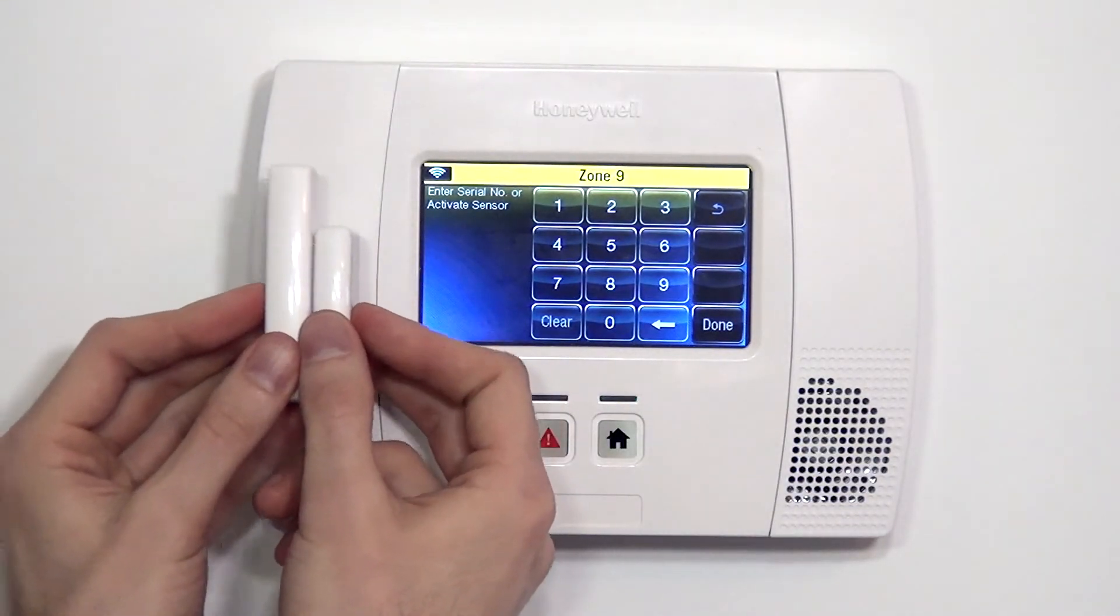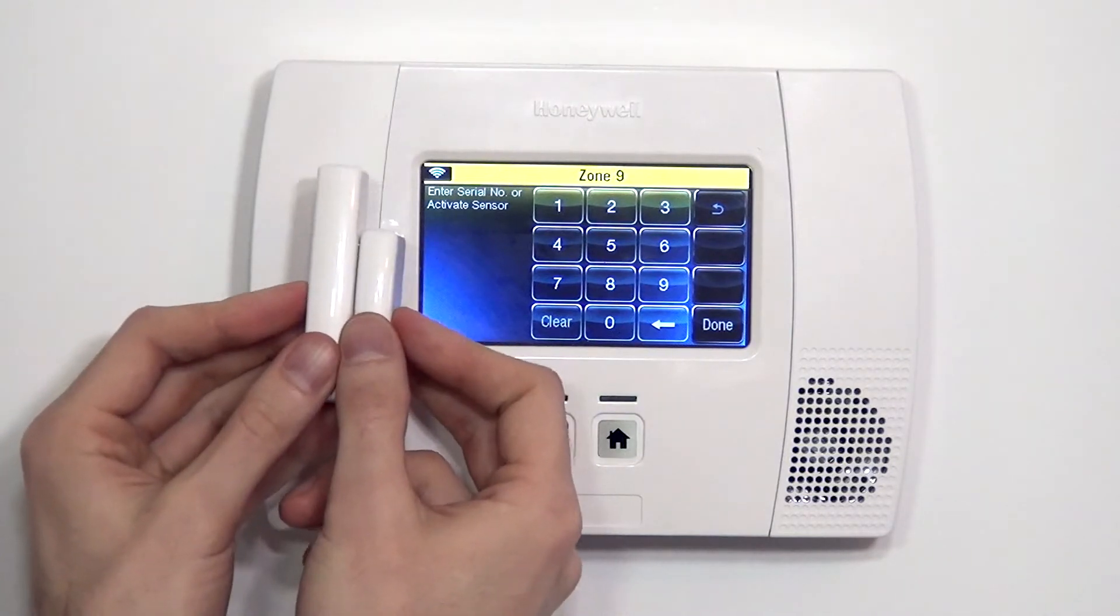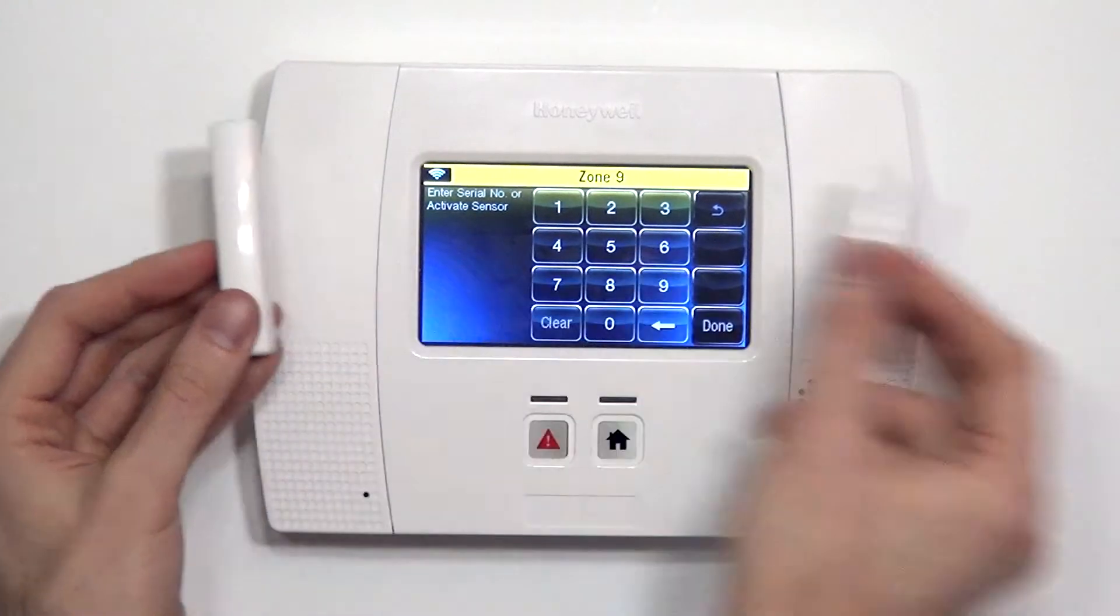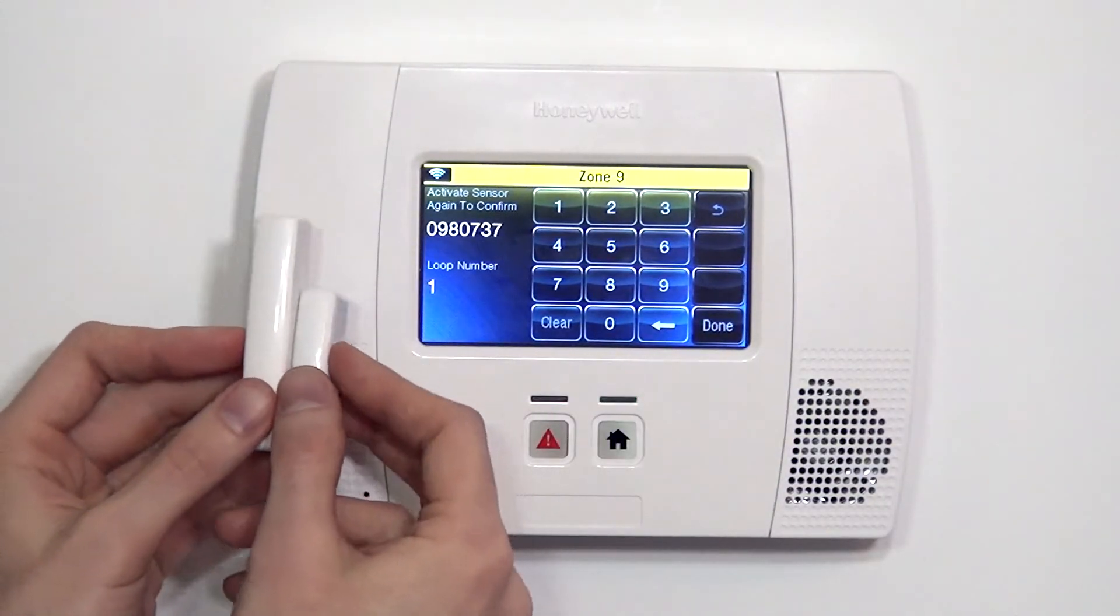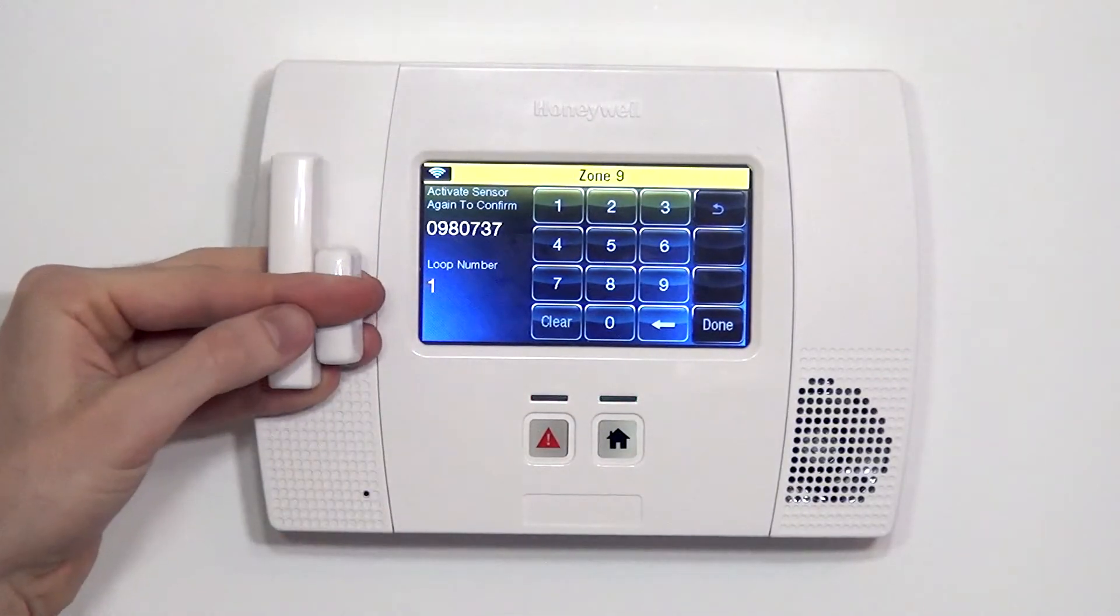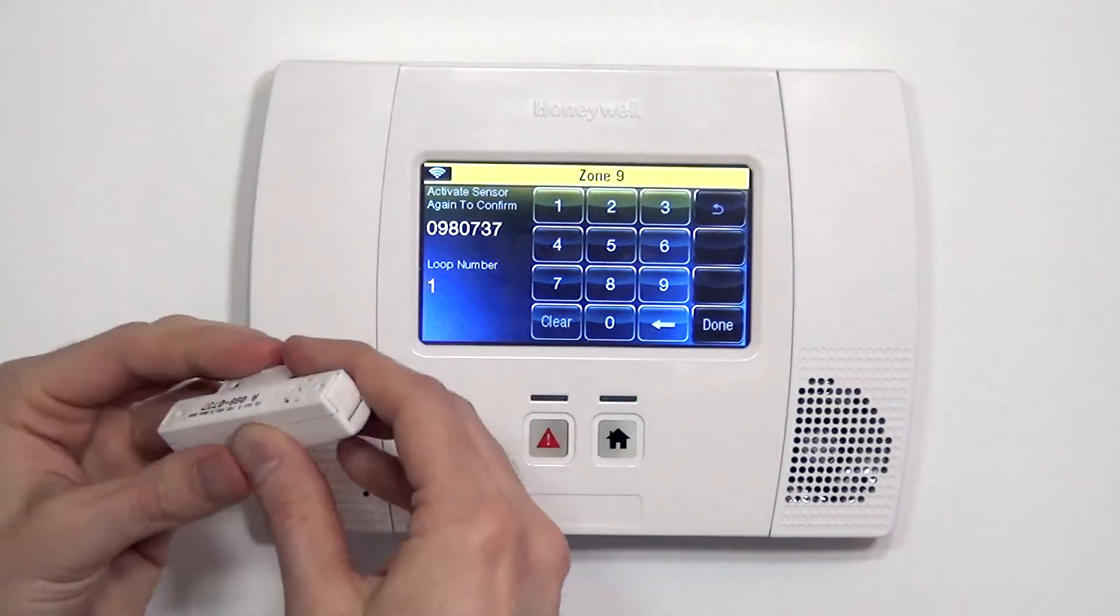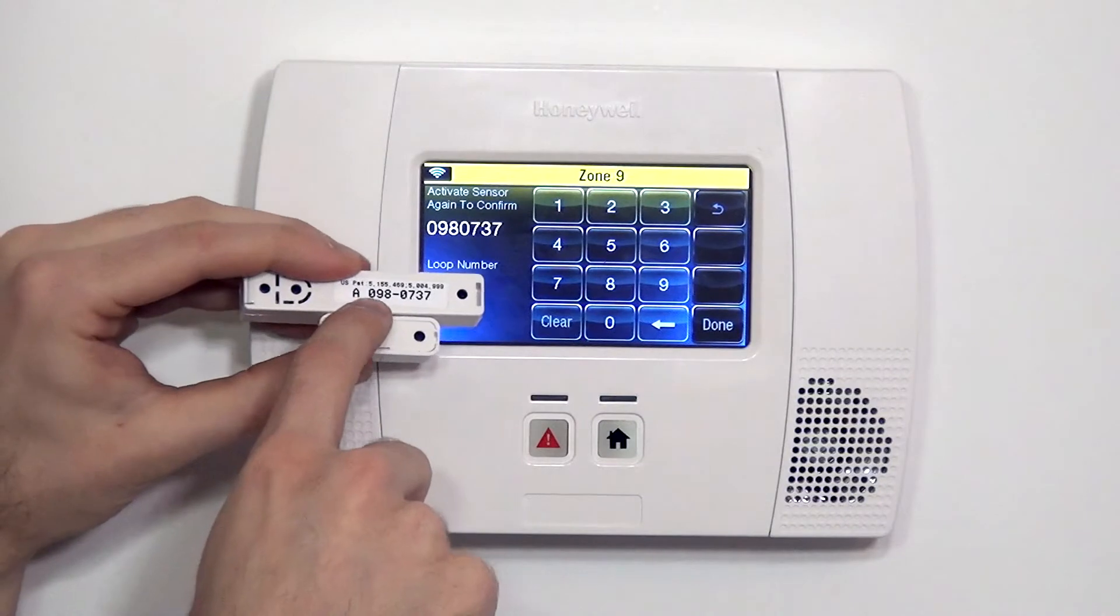If this is mounted on your door, you would simply be opening and closing your door. If you're doing it on the bench test, you simply fault the sensor by putting the magnet close, pulling it away. That's number two. We can see now we have loop number one, which is the proper loop when enrolling a 5820L. We have the verified serial number, which matches the serial number on the device, 0980737. And then we do one third and final activation.